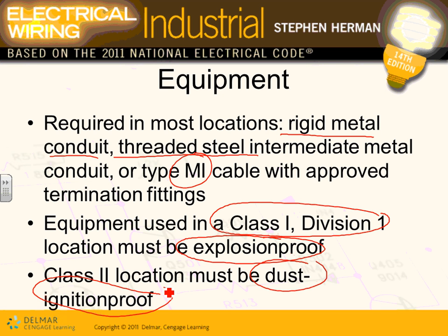One of them is explosion proof in a Class 1, Div 1, and typically Div 2. In a Class 2, Div 1, they use something called dust ignition proof. So when you buy, dollar-wise, times it by 5. If you need a panel like this, a dust ignition proof panel, if this costs you $500, times this by 5 when it comes to ignition proof or explosion proof. Do you guys see why it's so important to pay attention to it in terms of estimating, and project management, and managing a project in a hazardous location? Big deal.